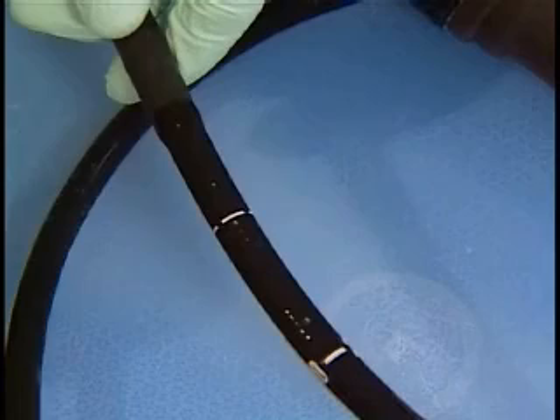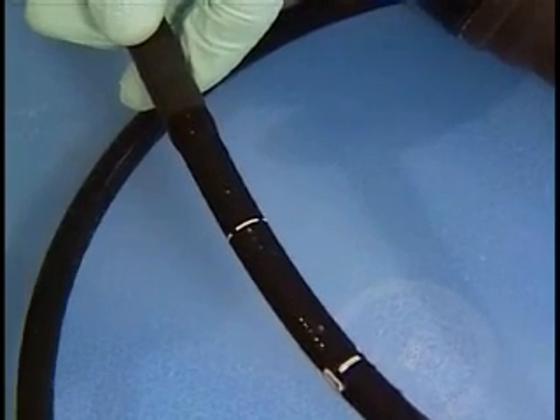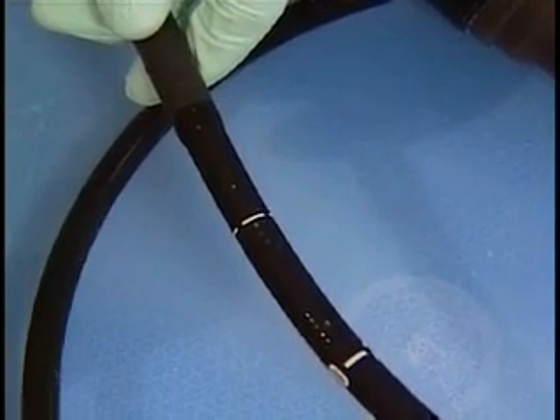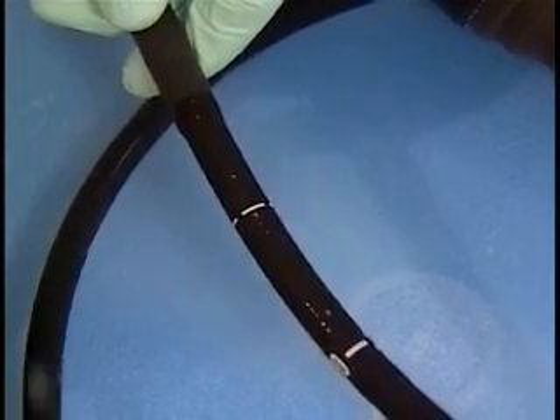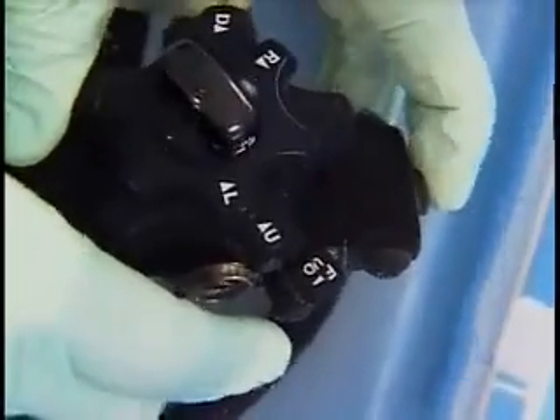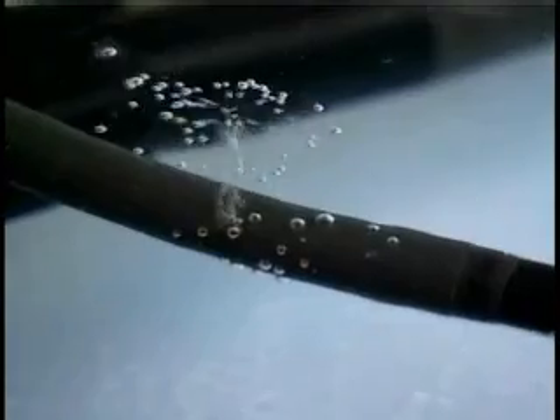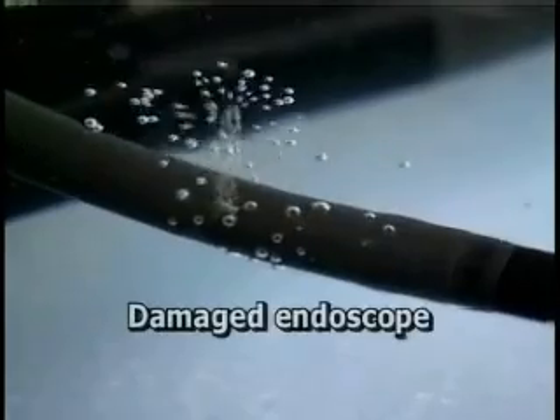Initially, you may see a few bubbles clinging to the insertion tube or coming out of a channel opening. These do not indicate a leak. Wipe away any bubbles clinging to the instrument. Also, manipulate the scope buttons to check for leaks. If you see no source of continuous bubbles, the endoscope is air and fluid tight. In contrast, if you do observe a continuous stream of bubbles, the endoscope is leaking.